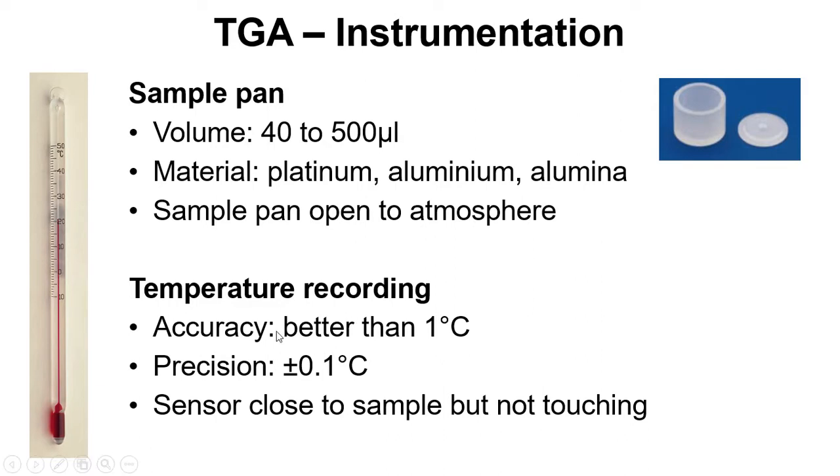Temperature recording accuracy is better than about 1 degree Celsius, with precision of ±0.1°C. As mentioned before, the temperature sensor is close to the sample but not touching it, and there's a couple of reasons for that.